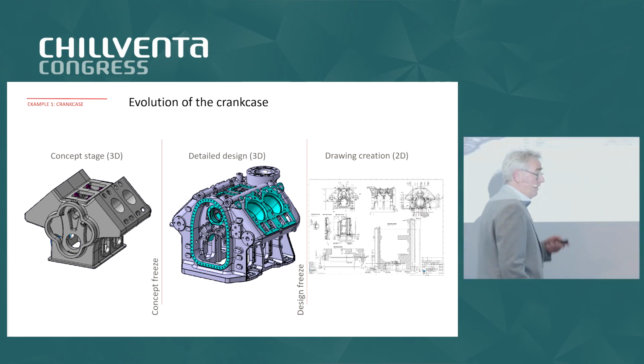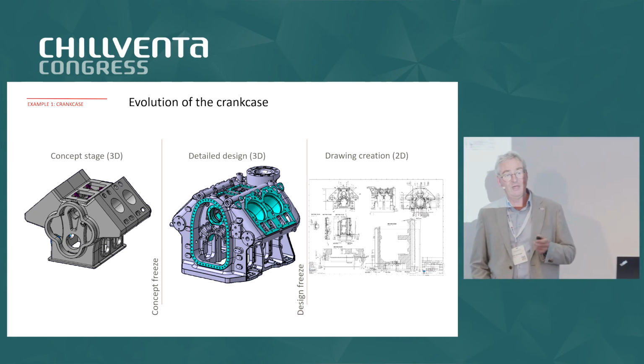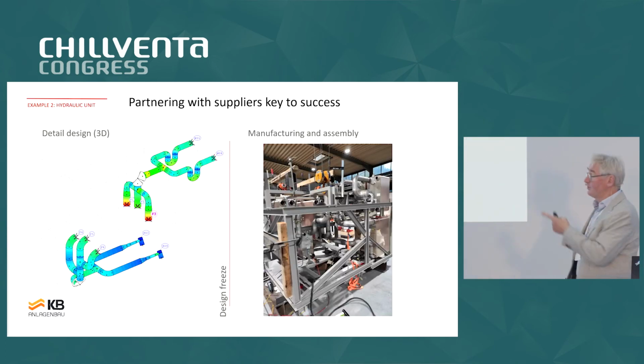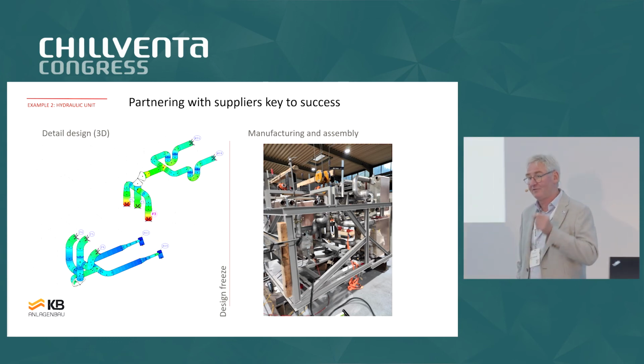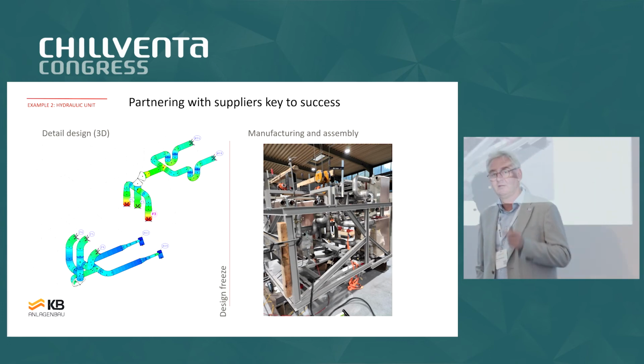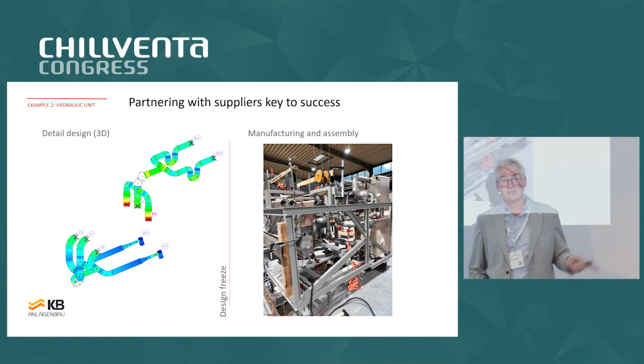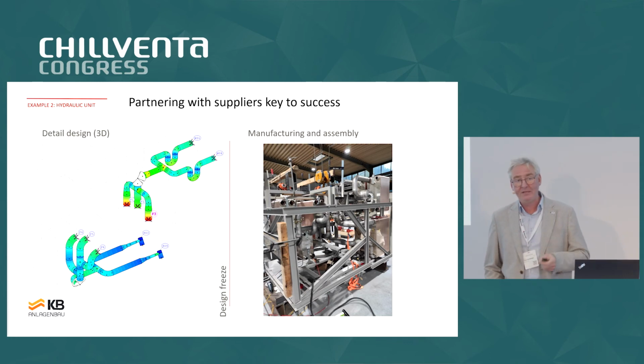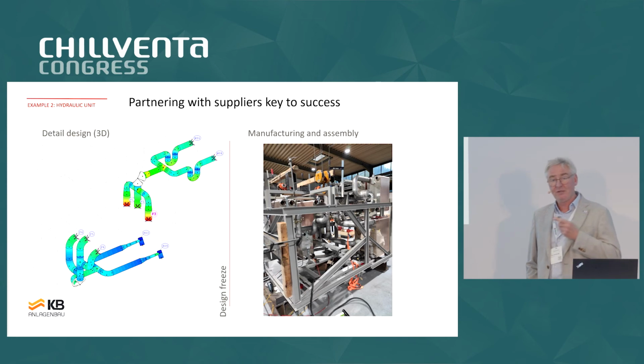Vice versa, another advice which we've seen a lot, we haven't developed a compressor, we have developed a heat pump. Because if you don't put in the entire hydraulics and all the details, the heat exchangers, the pumps, the expansion valves, the control, you lose 3 to 7% of efficiency just by not properly designing the heat pump to the compressor. We had a lot of discussions in the last couple of days over here, and that remains an issue that people just ask, can we buy your compressor? No, you can't. Because we need to actually make sure that the rest of the machine is working properly.